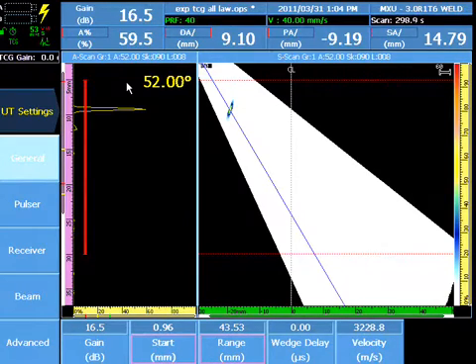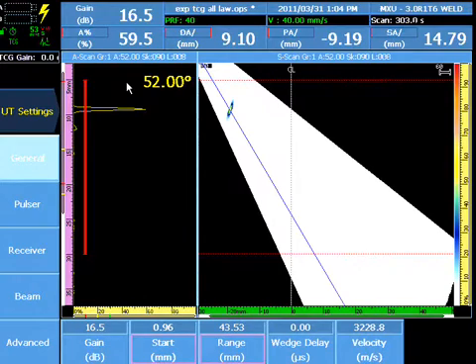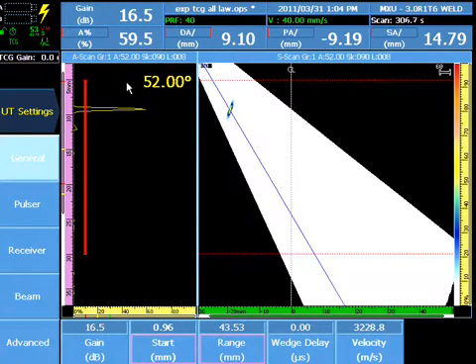Prior to using the TCG Wizard, the sensitivity wizard should be completed on a target in the area of interest of the inspection prior to entering the TCG wizard.